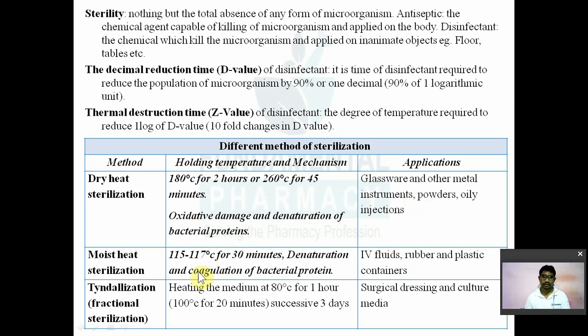Now moist heat: you have to use a temperature in the range of 115 to 117 degrees Celsius for 30 minutes. Okay, in the autoclave you use 121 degrees Celsius for 20 minutes. The pressure is 15 pound. The mechanism is denaturation and coagulation of bacterial protein. So the main mechanism for dry heat is oxidative damage and denaturation of bacterial protein. But in case of moist heat, it is mostly coagulation of bacterial protein and then denaturation. In dry heat, denaturation happens maximum, with oxidative damage and denaturation. Here coagulation will happen.